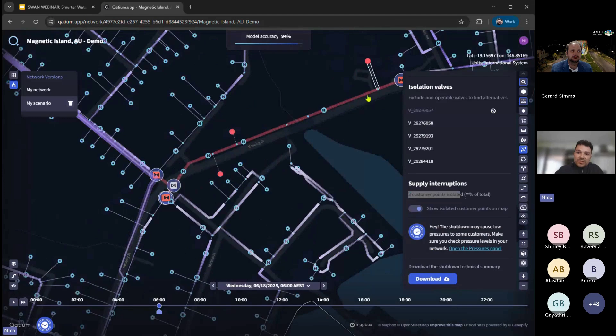You can see here, I'm zooming in. You get a summary of the affected customers, a list of valves you need to close to perform the shutdown, valves you need to open to reestablish supply if you have any alternative supply options, valves that are broken, and the full list of customer points and hydrants that will be affected by the shutdown.